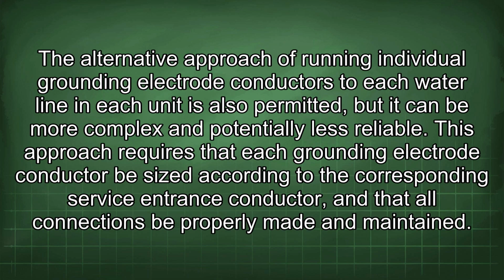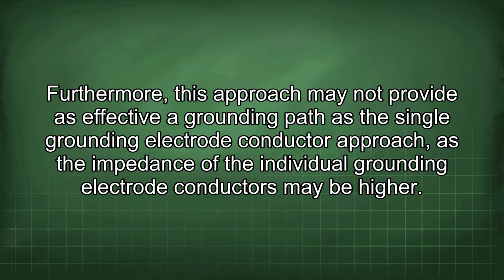The alternative approach of running individual grounding electrode conductors to each water line in each unit is also permitted, but it can be more complex and potentially less reliable. This approach requires that each grounding electrode conductor be sized according to the corresponding service entrance conductor, and that all connections be properly made and maintained. Furthermore, this approach may not provide as effective a grounding path as the single grounding electrode conductor approach, as the impedance of the individual grounding electrode conductors may be higher.